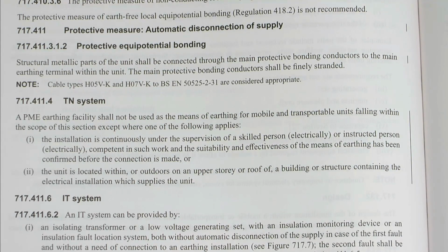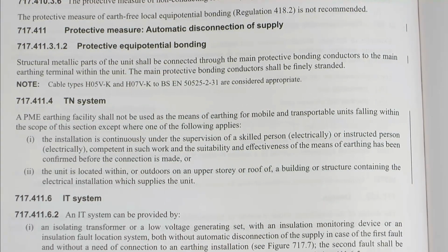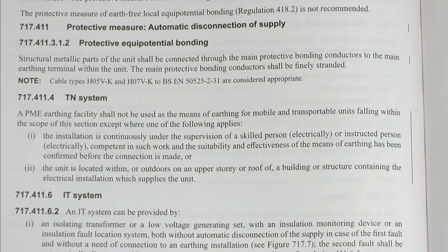This existed previously, but it's been rewritten and somewhat expanded. It covers the point that a PME earthing facility should not be used as the means of earthing for mobile and transportable units falling within the scope of this section. These two indents in particular have been expanded quite a lot: the installation must be continuously under the supervision of a skilled or instructed person competent in such work, and the suitability and effectiveness of the means of earthing must be confirmed before the connection is made, or the unit is located within or outdoors on an upper story or roof of a building or structure containing the electrical installation which supplies the unit. So it's just expanding on what was there essentially.